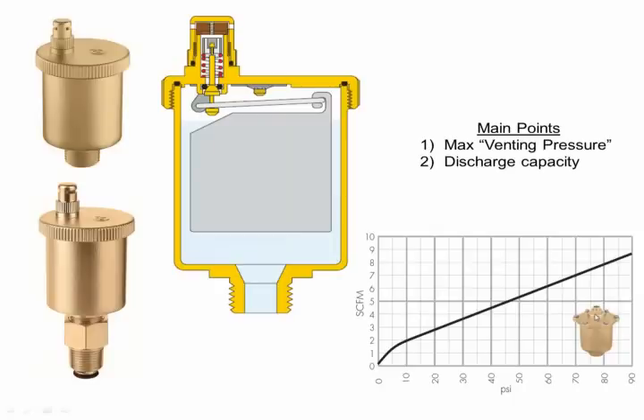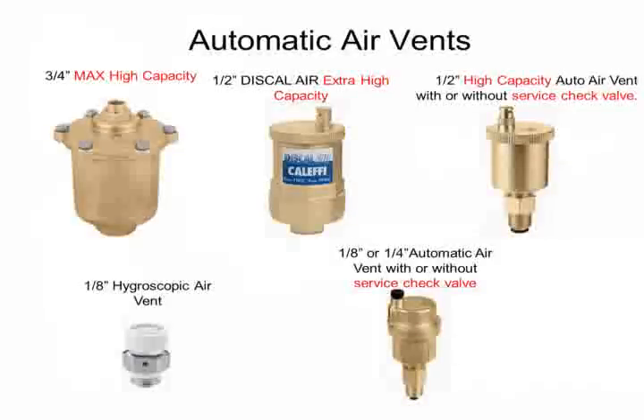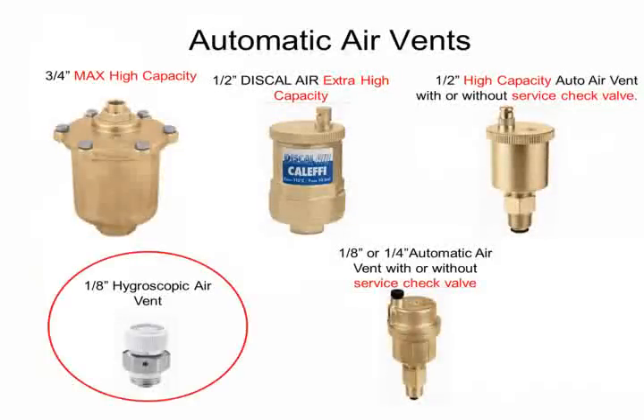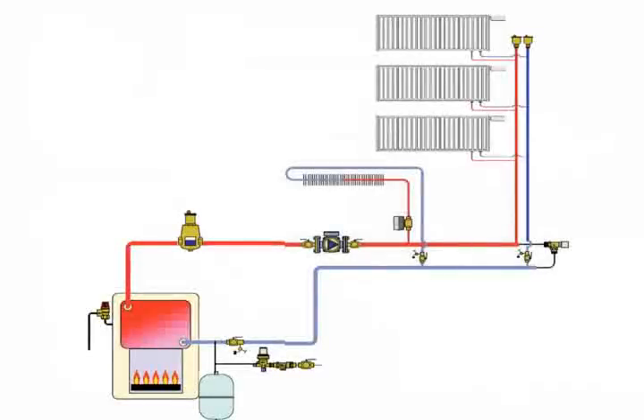Also the discharge capacity, so how much air can get out of that air vent. So here's one of our charts, and as an example, our high capacity air vent at 60 psi will rid itself of 6 cubic feet per minute.